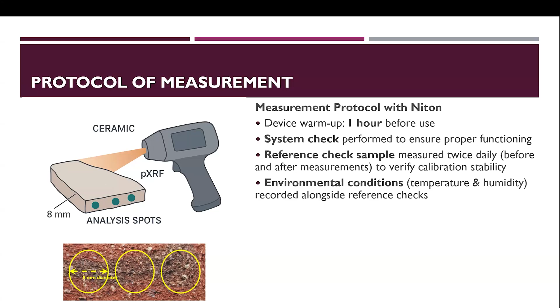For the ceramic samples, fresh breaks are prepared to provide the best results. These breaks must be at least 3 centimeters long and 1 centimeter wide to cover the 8 millimeter length of the equipment and to minimize the X-ray scattering. 3 measurements are performed on 3 different points on the fresh break due to the heterogeneity of the clay matrix of the ceramic material.